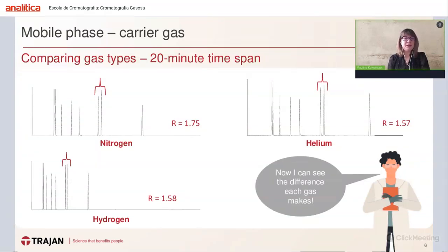We have also marked here the resolutions of the pair of peaks which we've chosen. And as you can see, the resolutions also differ between gases. So different gases will have a different impact on our analysis, on our resolution, as well as on the analysis time.